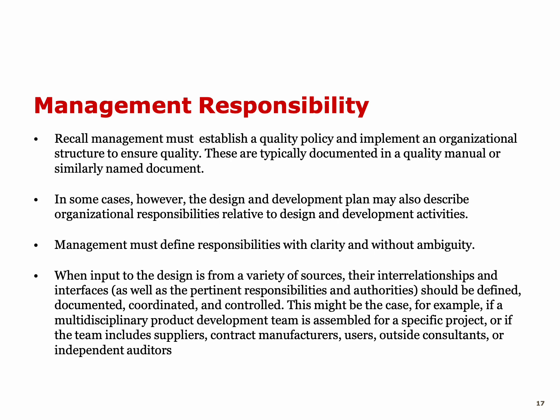We need to have a document or documented proof to show that we have an upper management, we have a management, and what are their responsibilities in order to make sure that the medical device that is being designed and prototyped and then tested and then put on the market is following the international standards and the regulations. Now, the management must define responsibilities with clarity and without ambiguity.